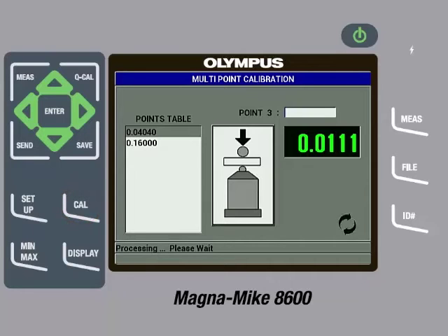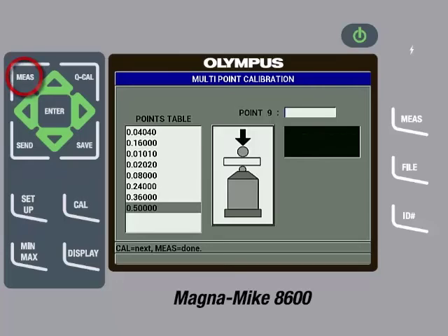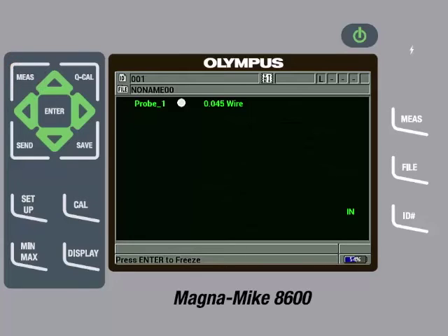Once the instrument is finished processing, we will use the arrow keys to change the value to the exact thickness of the shim, which in this case is 0.0101 inches or 0.257 millimeters. We will then press the cal key, which will add the thickness to the list of calibration points. We can then repeat this process for the other calibration standards until they are all added to the list of calibration points. Once they have all been entered, we can press the Measure key. We have now completed a full multi-point calibration.